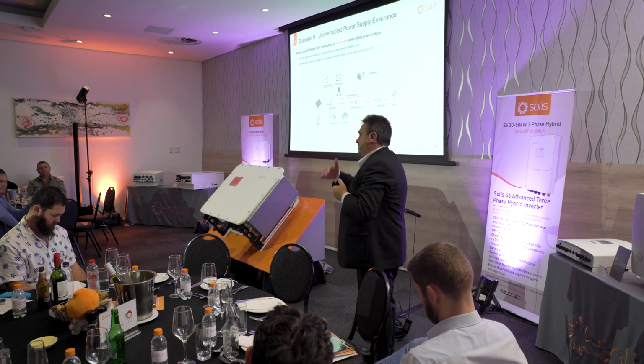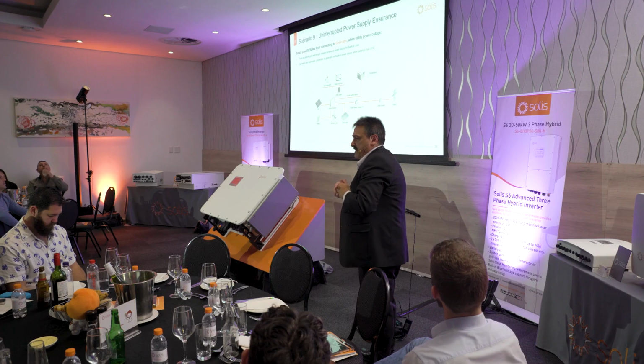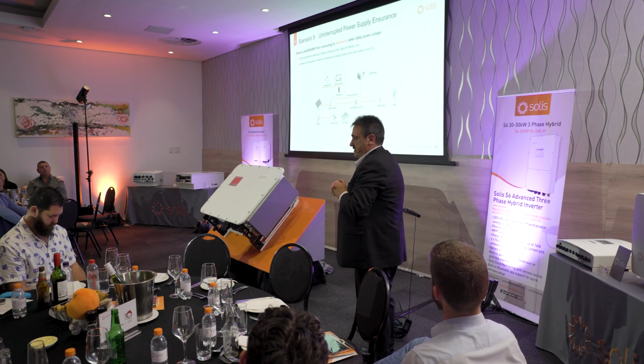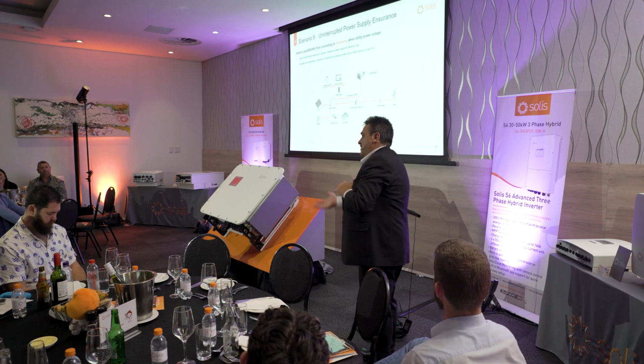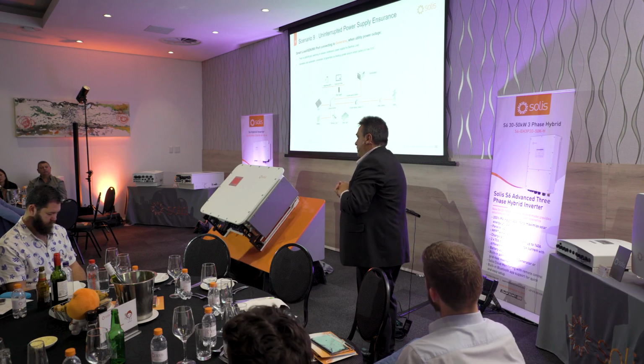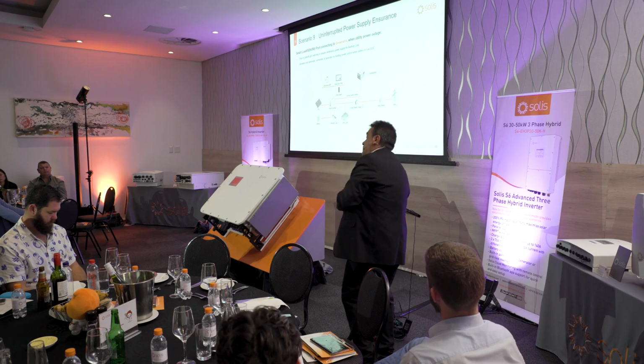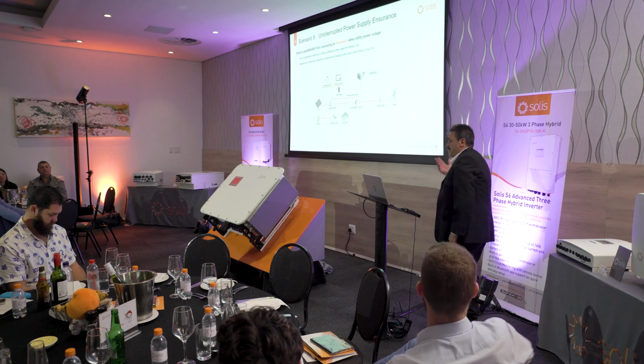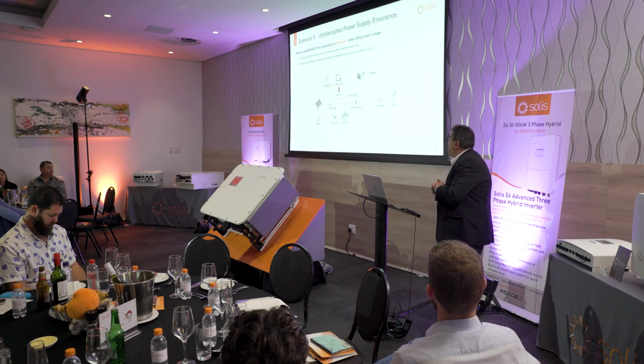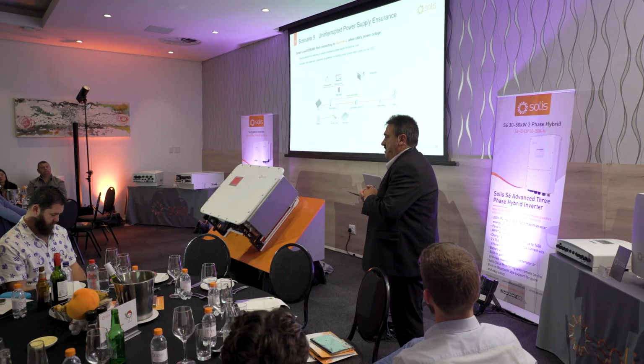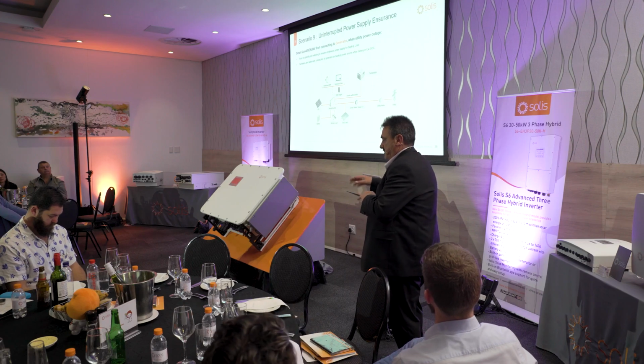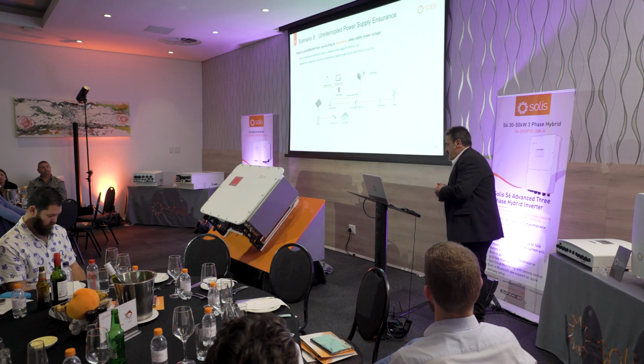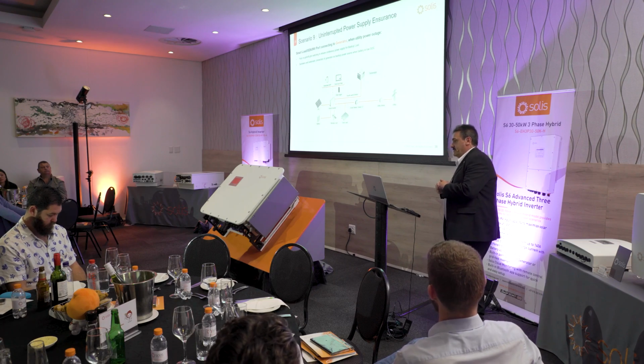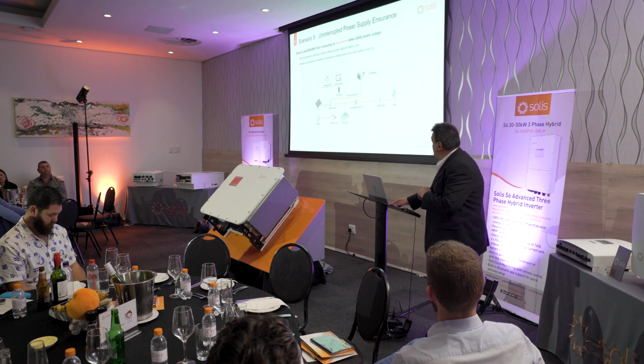It means that the inverter is saying, we've reached a certain SOC now, and I want you to help charge the batteries back up, because it's the middle of the night, or it's snowing in Cape Town, and we're not going to get any PV power soon, but I need to up the SOC of my batteries a bit. And normally you're not going to run that function to charge the batteries to 100%. It's purely to assist them until you can have PV assisted charging again. And then when it reaches the exit set point, it will open a relay and the generator will see that as a signal to shut down. Again, that can happen automatically if you've got the controller. On the residential systems, generally those don't have those controllers, so you are the starting signal and the shutting down signal.